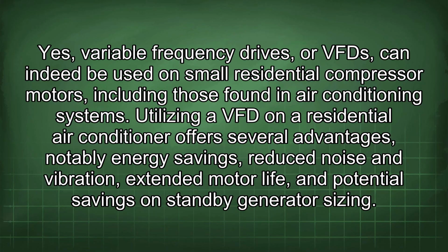Yes, variable frequency drives, or VFDs, can indeed be used on small residential compressor motors, including those found in air conditioning systems. Utilizing a VFD on a residential air conditioner offers several advantages, notably energy savings, reduced noise and vibration, extended motor life, and potential savings on standby generator sizing.